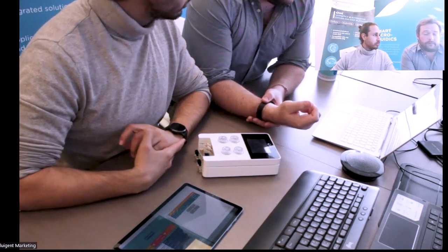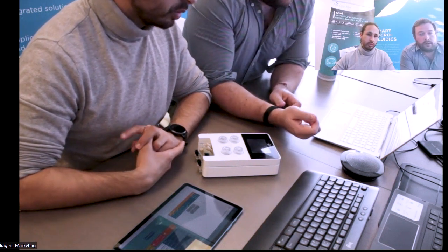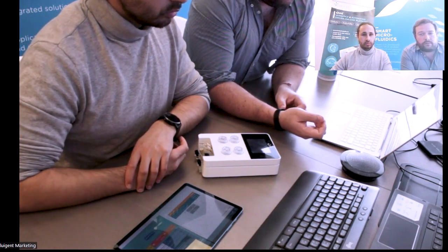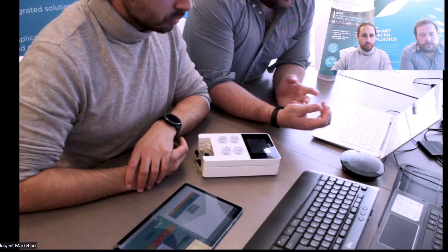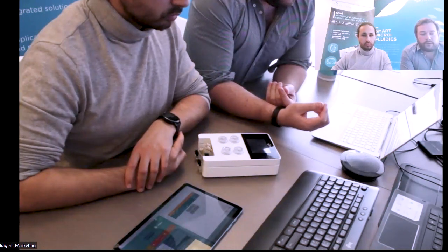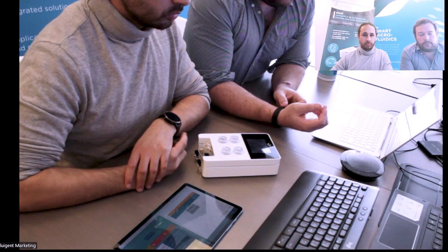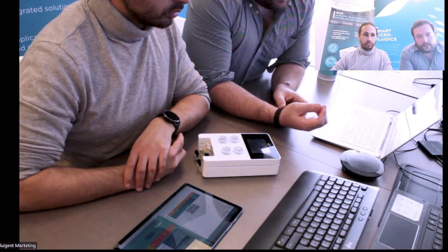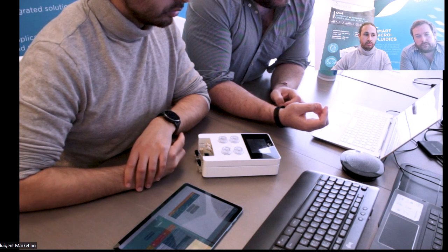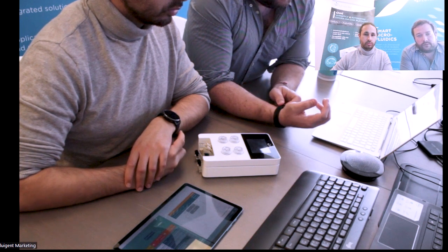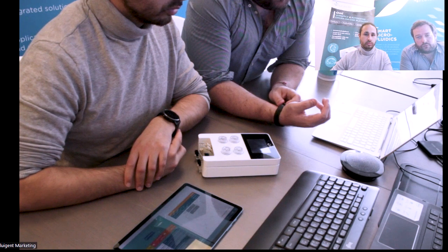So it would work with standard cell culture mediums, even with some other solution in it, like fetal bovine serum, a little bit diluted, that makes it a little bit more thick, maybe, and it will still not need a flow sensor reconfiguration. But I'm not sure a too thick solution would be compatible with the flow sensor itself. So I don't have a precise answer to this question, but I'm not really sure.